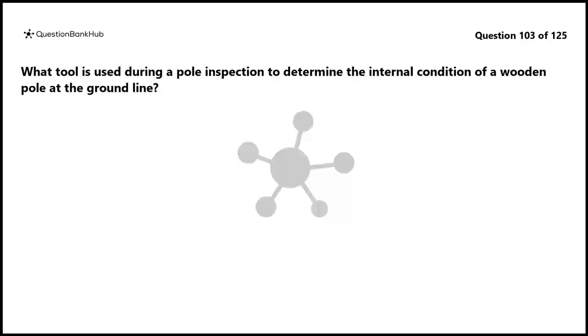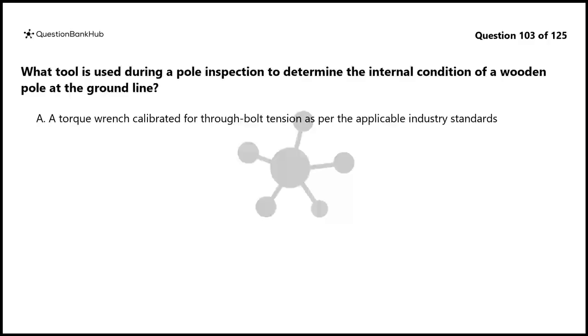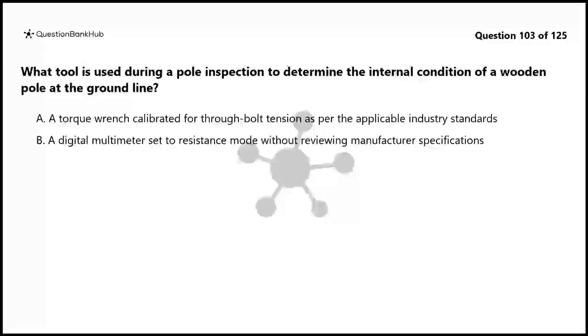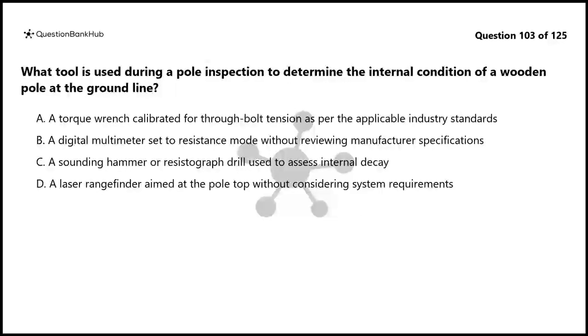Question 103. What tool is used during a pole inspection to determine the internal condition of a wooden pole at the ground line? A. A torque wrench calibrated for through-bolt tension as per the applicable industry standards. B. A digital multimeter set to resistance mode without reviewing manufacturer specifications. C. A sounding hammer or resistograph drill used to assess internal decay. D. A laser rangefinder aimed at the pole top without considering system requirements.